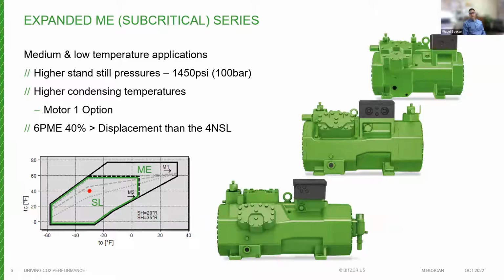A completely new product that's going to be offered and released next year in 2023 are the 4- and 6-cylinder ME series subcritical compressors. The ME series compressors have a standstill pressure of 1450 psi on both the high and low side. This feature, in conjunction with the higher horsepower motors, allows a significant increase in condensing temperatures on the low side of the CO2 system, increasing design options for engineers who are coming up with solutions for their customers. For reference, the SL series has a standstill pressure of 435 psi on the low side, and 770 psi on the high side.